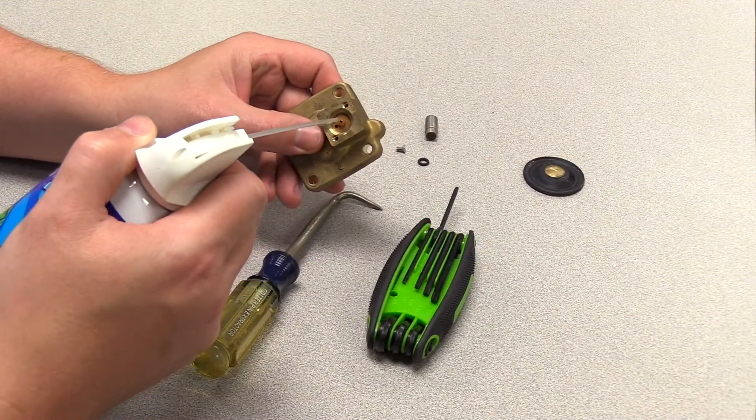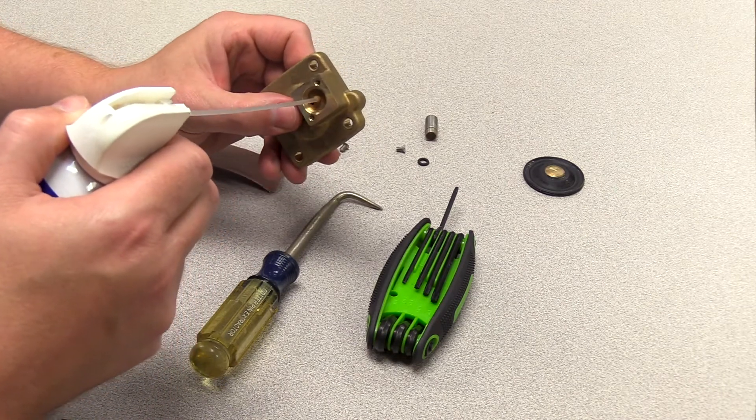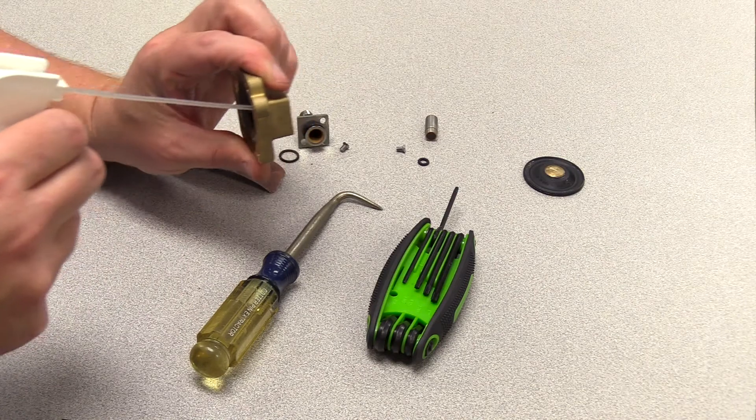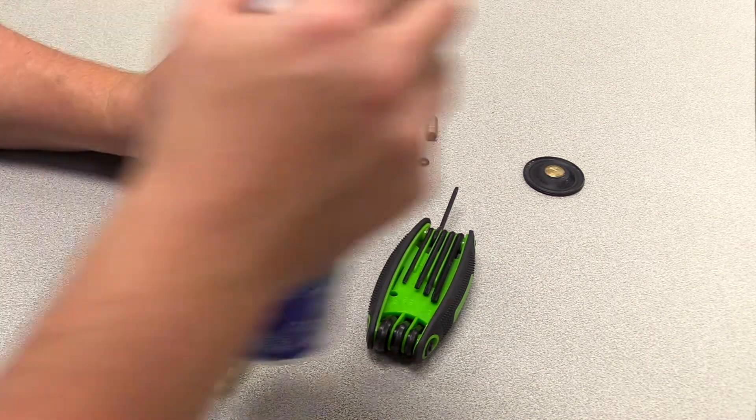Use a small wire or compressed air to clean the pilot orifice. Air will come out of the back of the valve top. When your valve does not close, many times the pilot orifice will have debris in it.